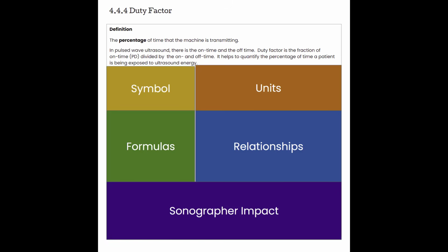What this ends up doing is helps to quantify the amount of time that a patient is actually being exposed to ultrasound energy. So they're really only getting it during the pulse, which is a very, very small fraction of time. But the duty factor tells us what that fraction or percentage is.